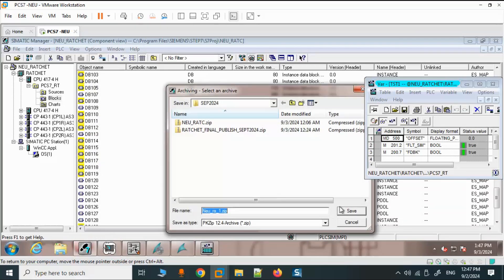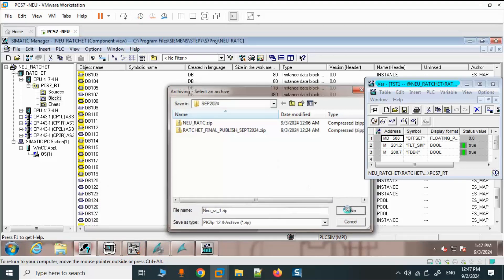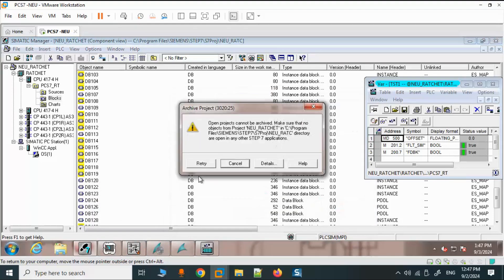You should be able to archive your project. But when these components used in the project — like the variable table, WinCC project, CFC chart — are open, you may receive this error: 'Archive project', message number 30 20 25.